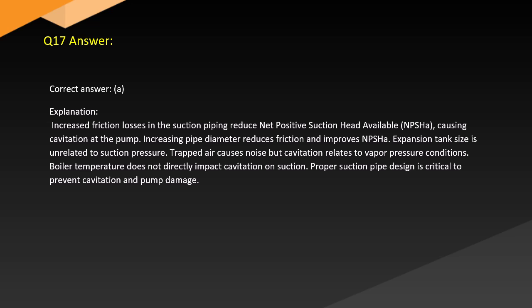Answer. Correct answer, A. Explanation. Increased friction losses in the suction piping reduce net positive suction head available, NPSHa, causing cavitation at the pump. Increasing pipe diameter reduces friction and improves NPSHa. Expansion tank size is unrelated to suction pressure. Trapped air causes noise, but cavitation relates to vapor pressure conditions. Boiler temperature does not directly impact cavitation on suction. Proper suction pipe design is critical to prevent cavitation and pump damage.